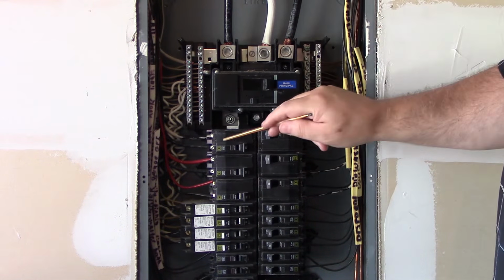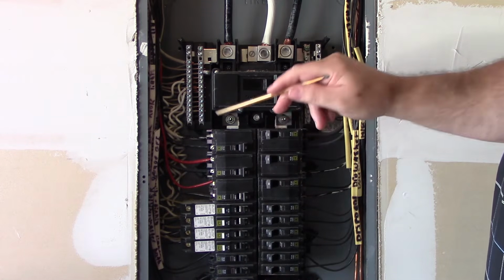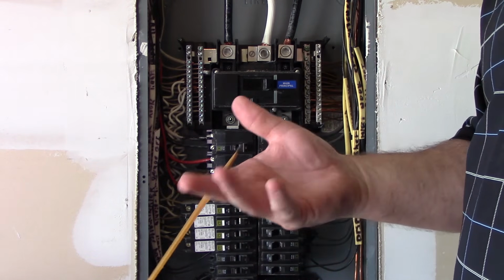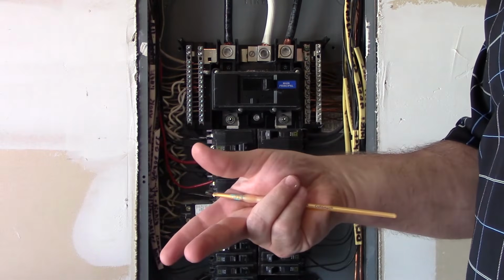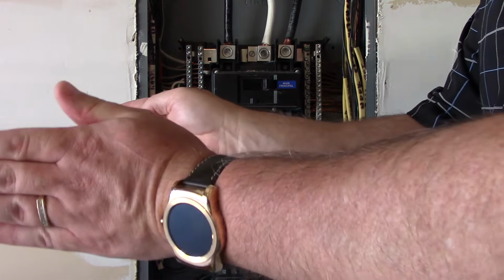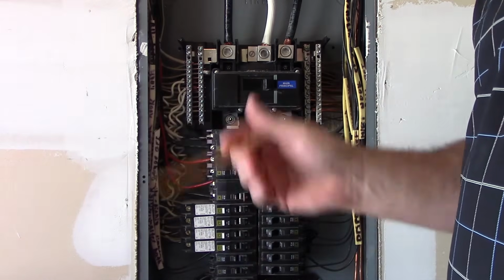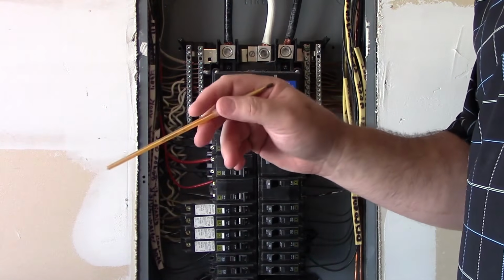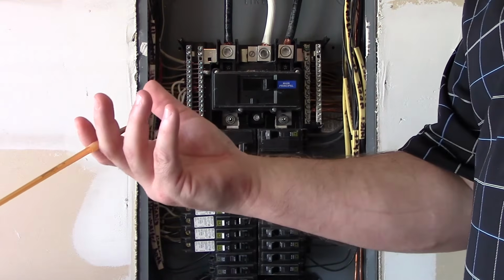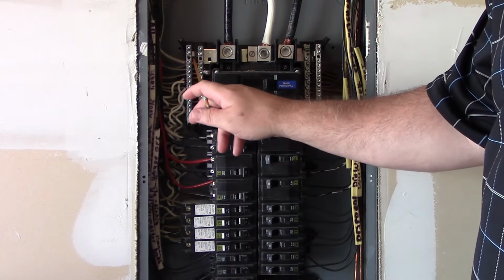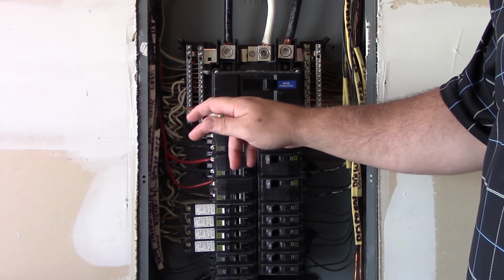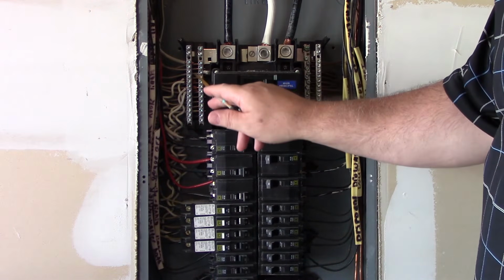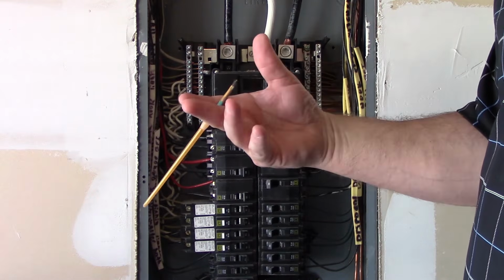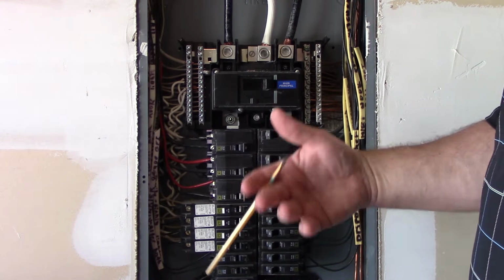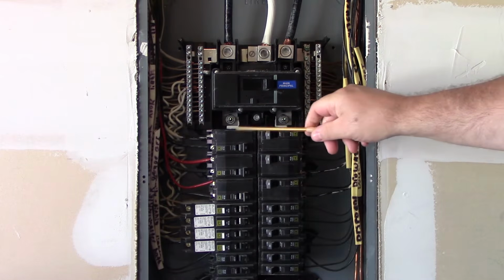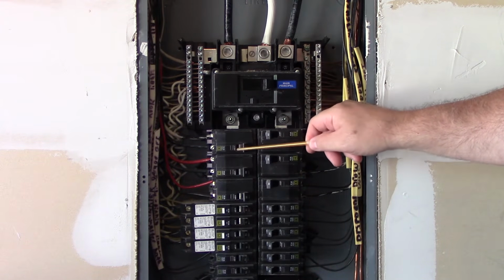Here, A, B. Okay? So what happens is if it's a multi-wire branch circuit, like a 14-3 or a 12-3 where I have a red, a black, and a common white, it's going out to two separate circuits, and they split off. Like bedroom A, bedroom B. Red goes to A, and black goes to B. The neutral is the common conductor that comes back. One, we want to make sure it's on its own lug. It's not ganged up with anybody. And that's why we're looking for brownouts and things on the insulation that might have discolored, because we might have what's called an improper multi-wire branch circuit. So the proper way to do it is to make sure that they are side by side with the handle tie.